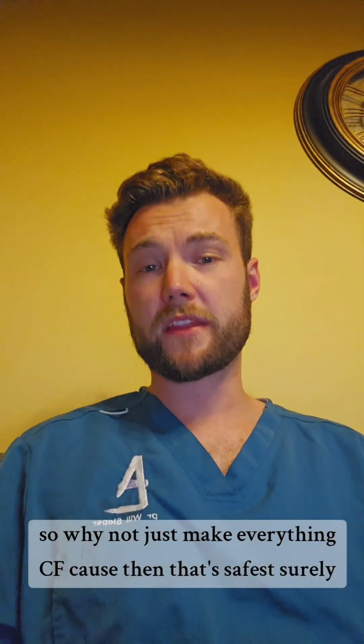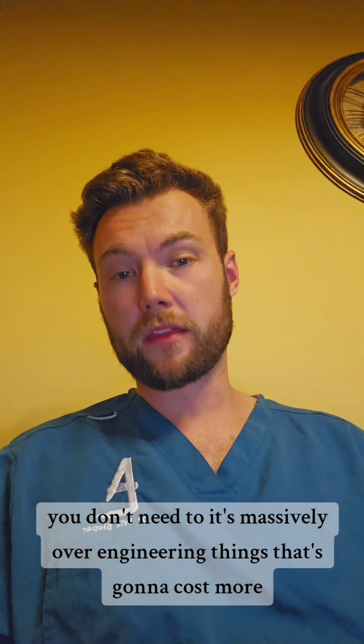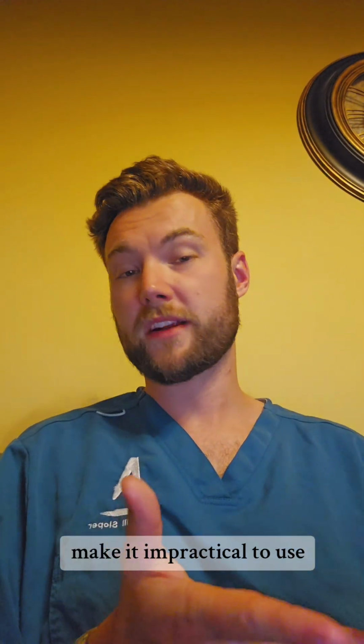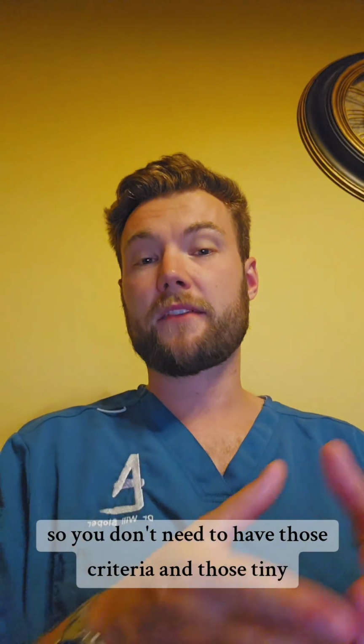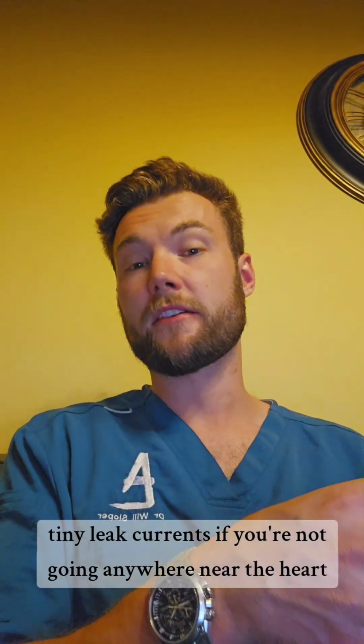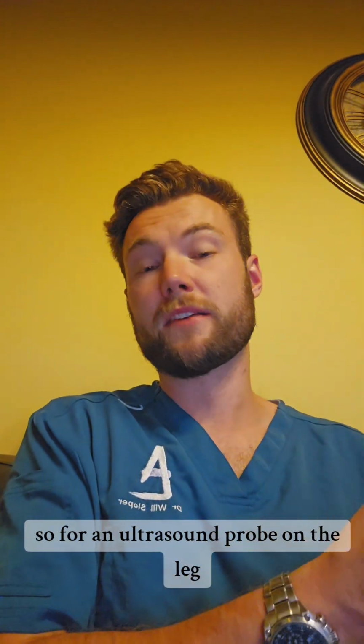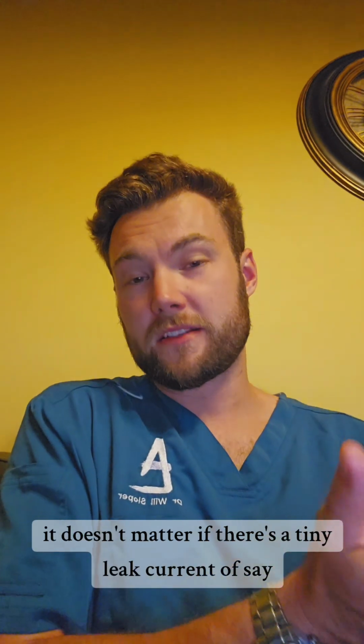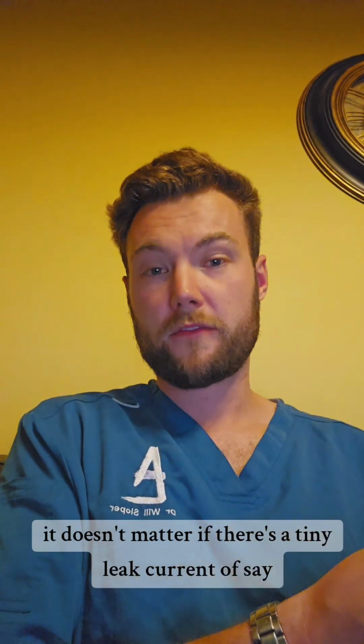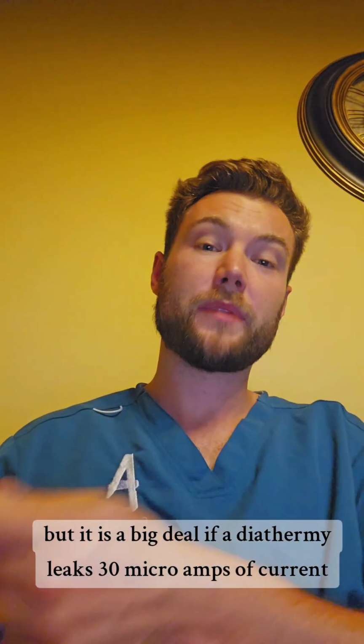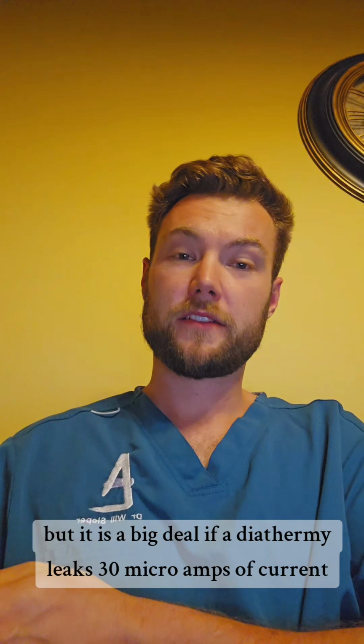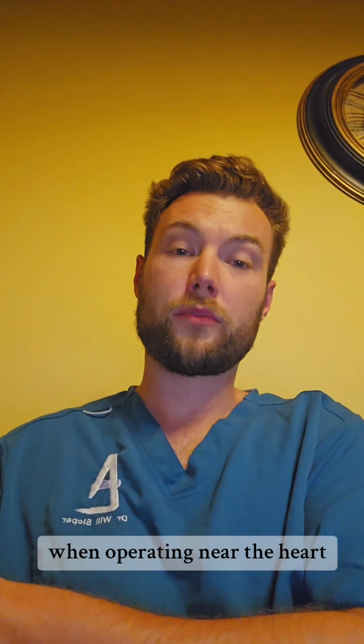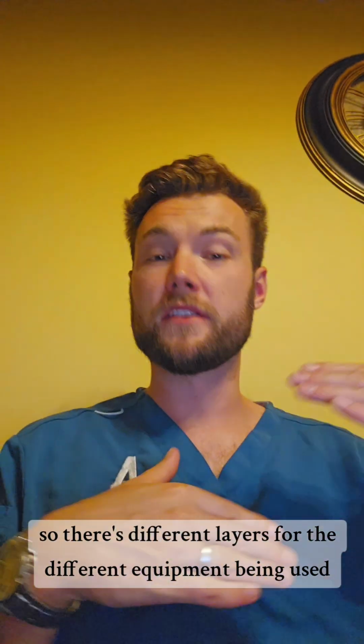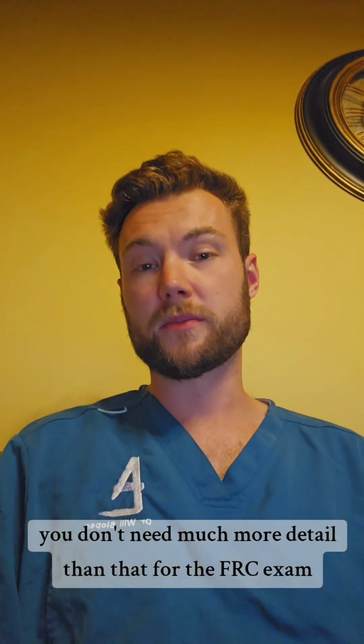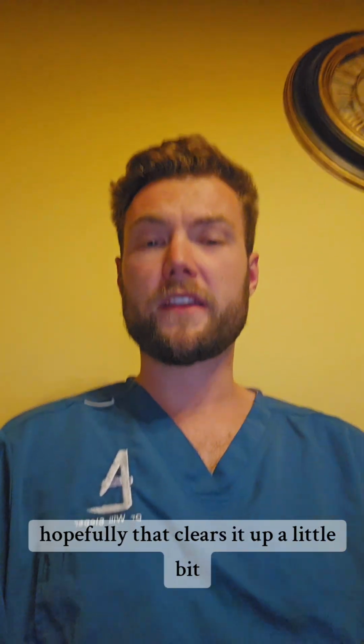So why not just make everything CF? Because then that's safest, surely. You don't need to. It's massively over-engineering things that's going to cost more, make it impractical to use. So you don't need to have those criteria and those tiny, tiny leak currents if you're not going anywhere near the heart. So for an ultrasound probe on the leg, it doesn't matter if there's a tiny leak current of, say, 70 microamps, but it is a big deal if a diathermy leaks 30 microamps of current when operating near the heart. So there's different layers for the different equipment being used. You don't need much more detail than that for the FRCA exam. Hopefully that clears it up a little bit.